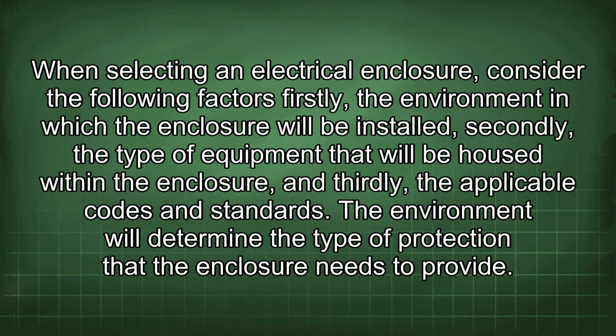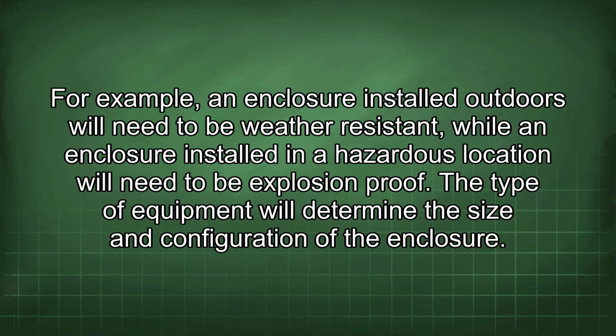When selecting an electrical enclosure, consider the following factors. Firstly, the environment in which the enclosure will be installed. Secondly, the type of equipment that will be housed within the enclosure. And thirdly, the applicable codes and standards. The environment will determine the type of protection that the enclosure needs to provide. For example, an enclosure installed outdoors will need to be weather resistant, while an enclosure installed in a hazardous location will need to be explosion proof.